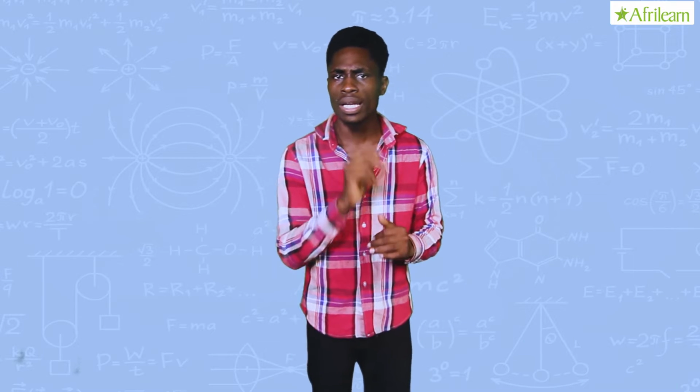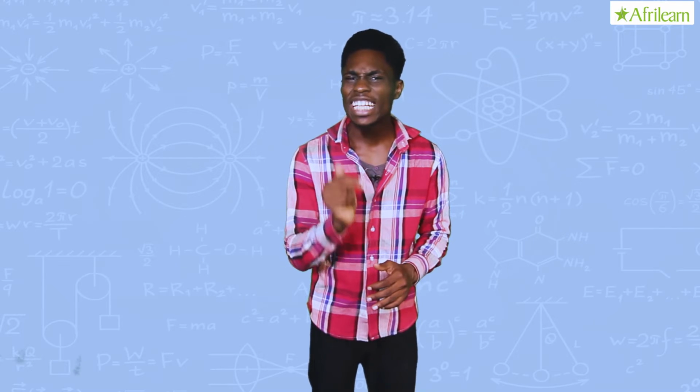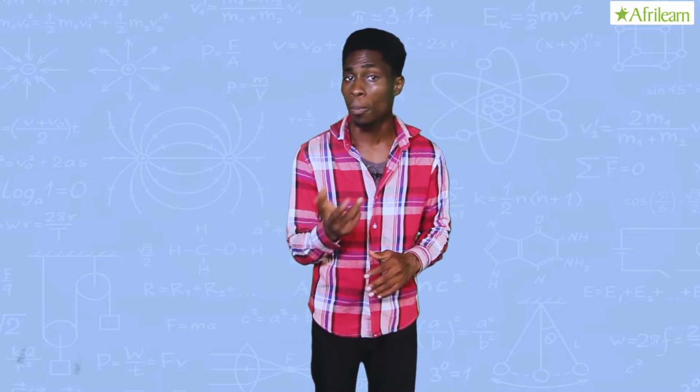Now, in this type of battery, a lead cell consists of two electrodes composed of lead compounds immersed in an electrolyte of dilute sulfuric acid. The active materials of the electrodes are deposited as coating on supporting lead grids. The electrodes consist of one or more grids or plates, anode and cathode plates being set alternately face to face.